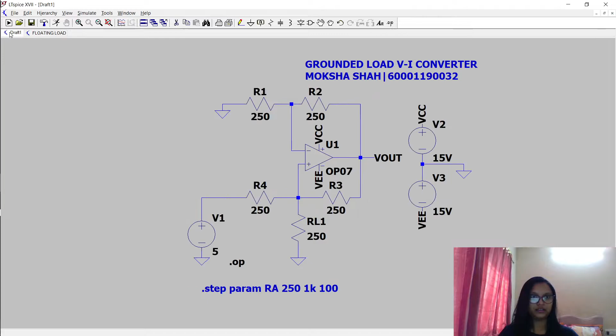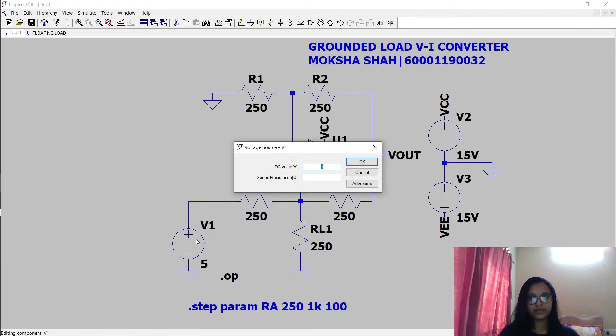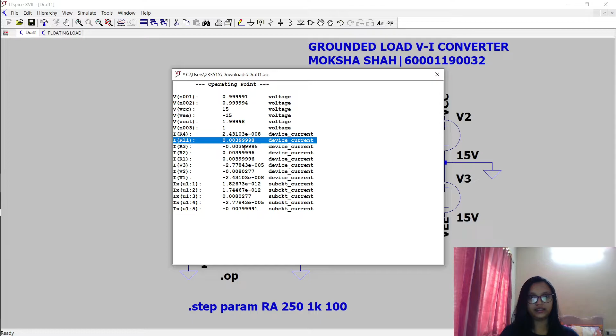In the grounded, I'll just open my circuit diagram. So this is for the grounded. Over here I've taken the value of RL as 250, as I have told you already. You can take any value of RL, just see that it's not beyond 600. So if I run, yes, for IL you are getting 19.439 milliamps, that is approximately 20 milliamps, and at 1 volt you are getting 3.9999, that is approximately 4 milliamps, matching with the theoretical values.